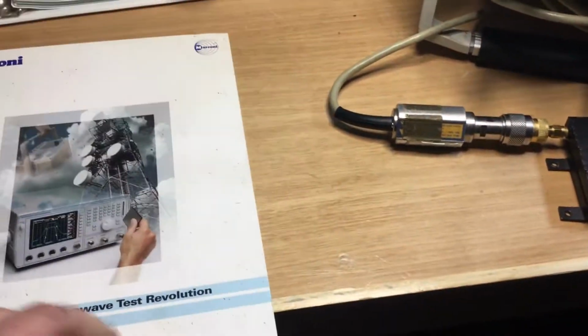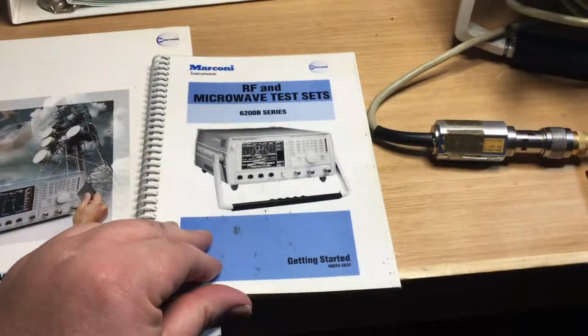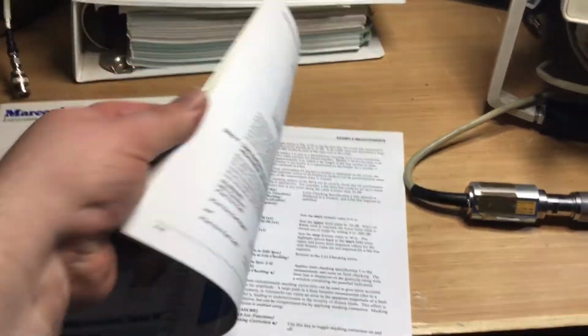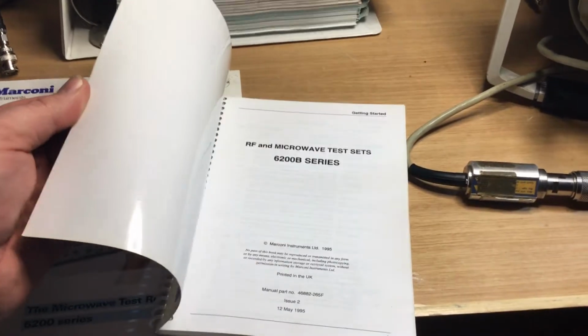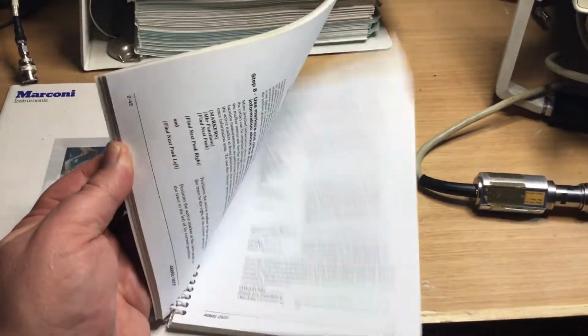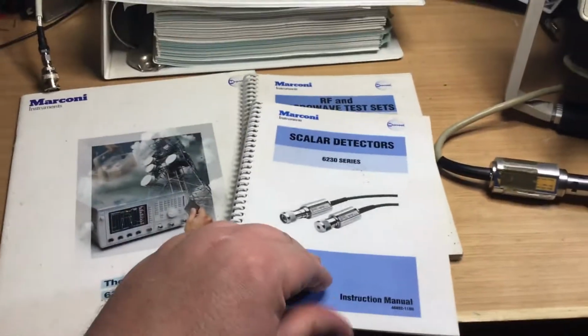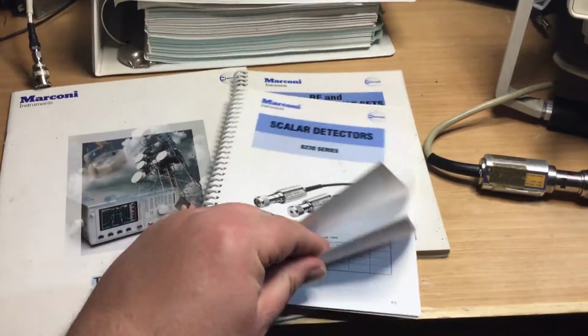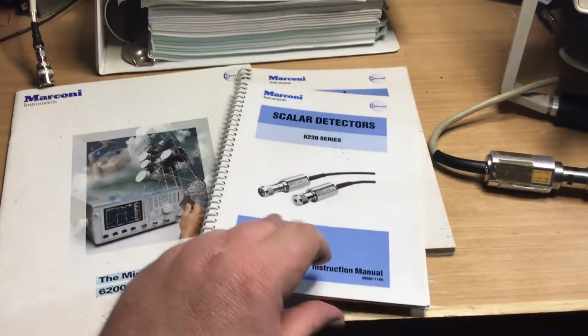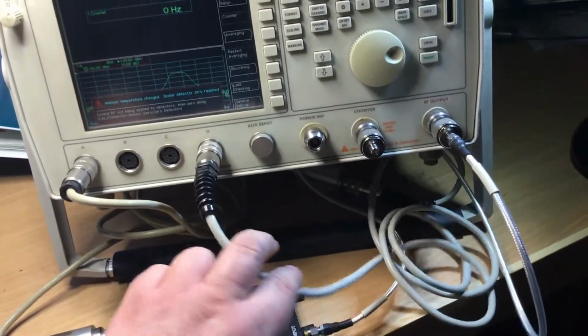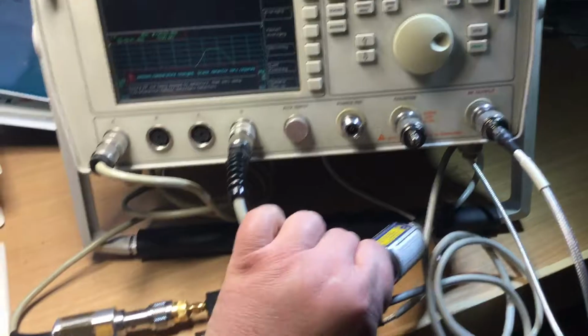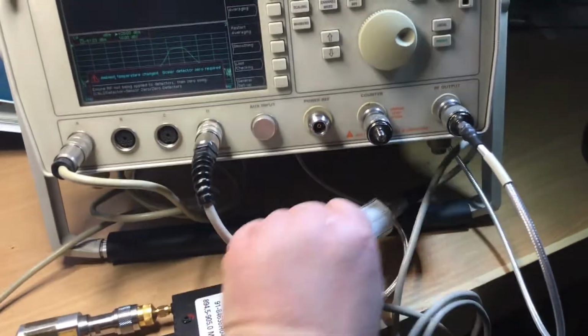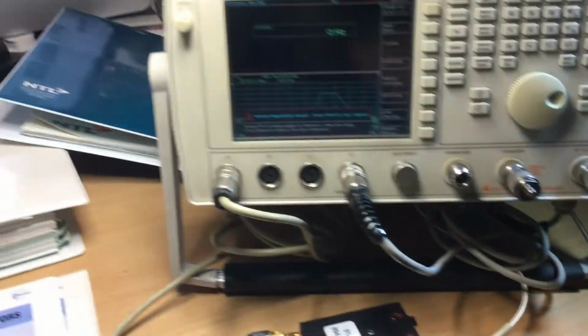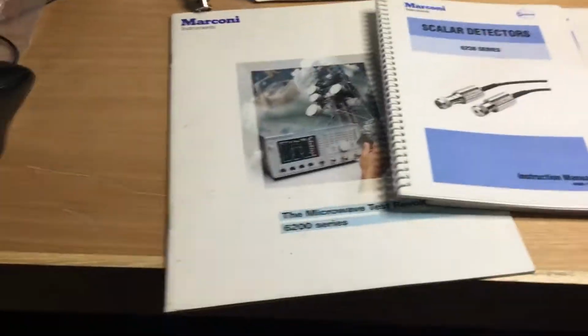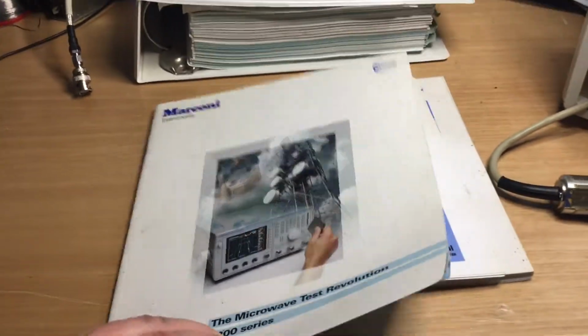So, as well as that, we've got a manual here which is the getting started guide for the instrument as well, which gives you a little rundown of how to do certain tests and measurements. Then we've got a manual on scalar detectors, because this instrument takes two different types of detectors. It takes a scalar detector, and then it also takes RF power detectors as well, which we'll look at a bit later in the video of measuring RF power with the inbuilt power meter.